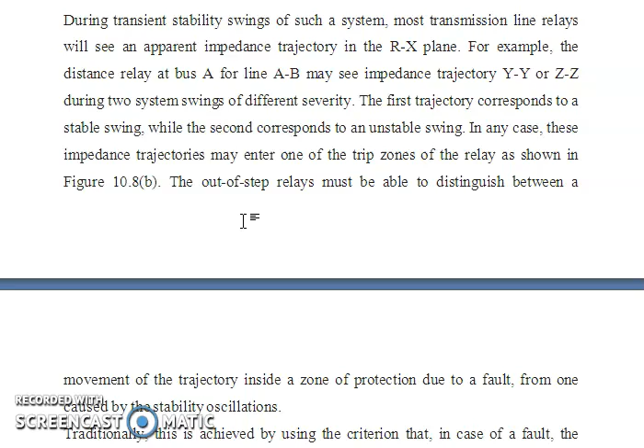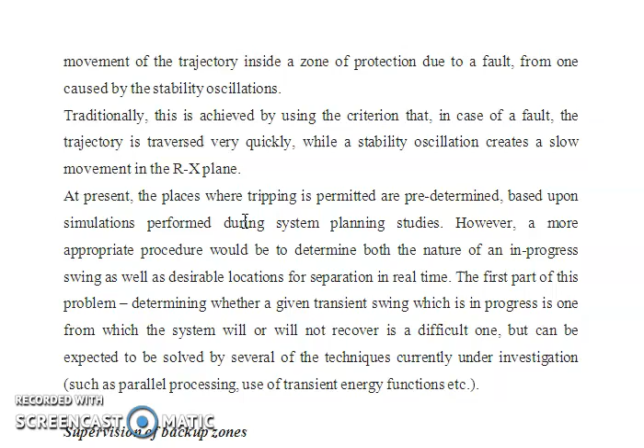Now in the present scenario, the place where tripping is permitted is predetermined based upon simulations performed during system planning studies. However, a more appropriate procedure would be to determine both the nature of an in-progress swing as well as the desired location for separation in real time. The first part of this problem, determining whether a given transient swing in progress is one from which the system will or will not recover, is a very difficult one, but can be expected to be solved by several of the techniques currently under investigation, such as parallel processing, use of the transient energy function, etc.